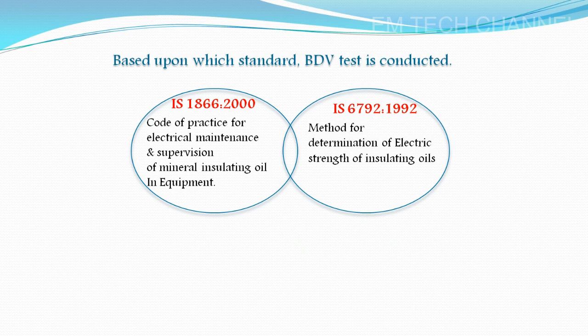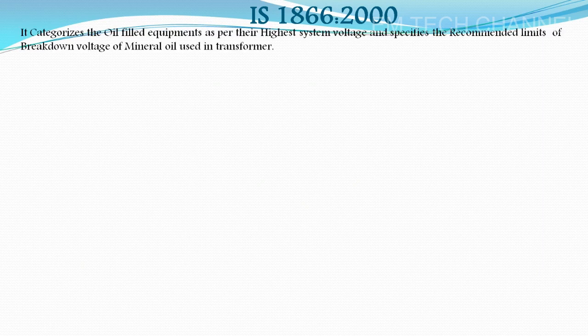In this, instead of transformer oil, it is given as mineral insulating oil, because the oil is not only used for a transformer, it is also used for current transformers, potential transformers, as well as for oil filled circuit breakers and on-load tap changers. So the generic name given is mineral insulating oil. First we will see the abstract of IS 1866-2000.